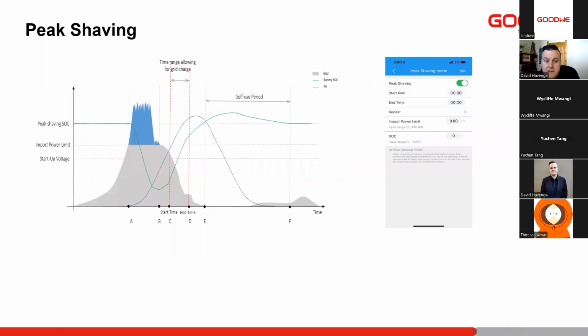And these devices can also work in peak shaving mode. So if you have customers with kVA billing and they want to reduce that peak demand from the utility supplier, they can install this device and configure it. What you'll do is you'll set your limit. So once your consumption reaches X amount, it will start to discharge the battery for any amount that's above X.